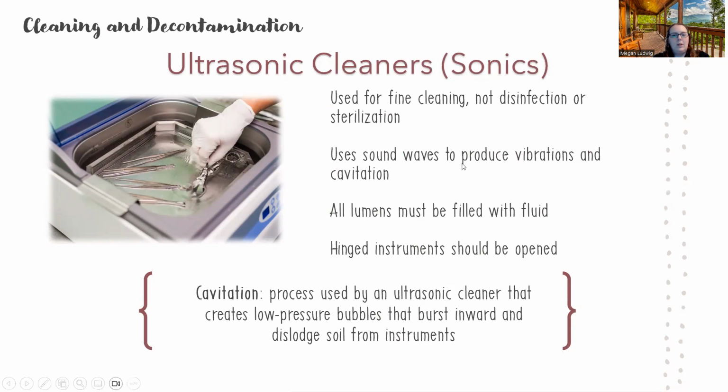So what it uses is actually sound waves. You put it in here and it shakes it really, really fast with sound waves. And it produces something called cavitation. So cavitation, if you look down here, is basically causing little microscopic air bubbles to burst inward, and as it's bursting, removes debris off of the instrument, which is kind of cool in how that works.